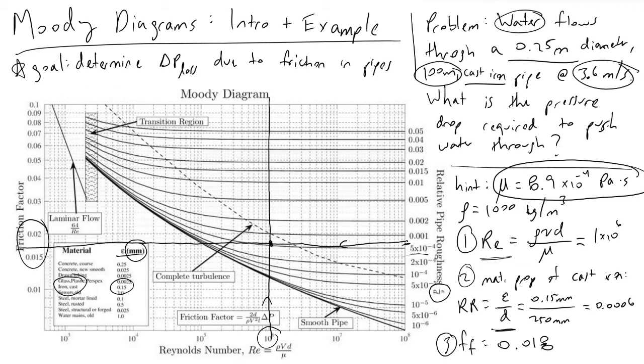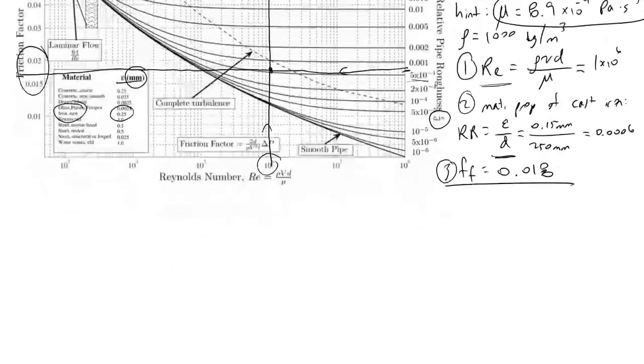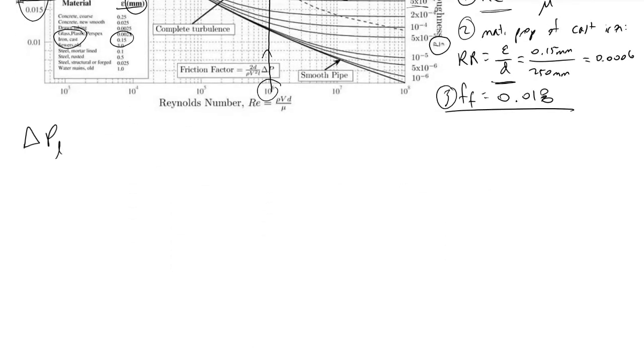Friction factor defined, we now know with the friction factor we can determine what our pressure loss will be. Delta P loss is equivalent to your friction factor times the length of your pipe divided by your diameter of your pipe times one half times the density of your fluid times the velocity of your fluid squared. If you plug in the numbers, we will arrive at a value of 93 kilopascals.